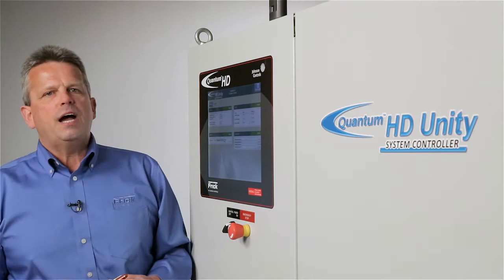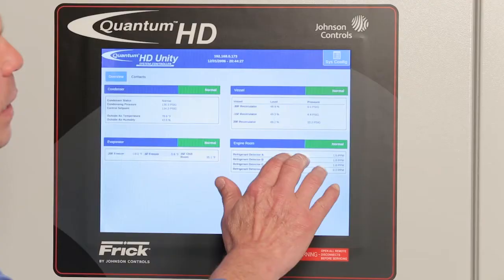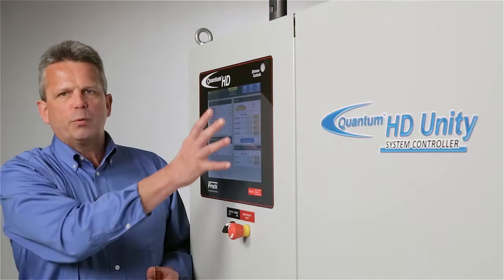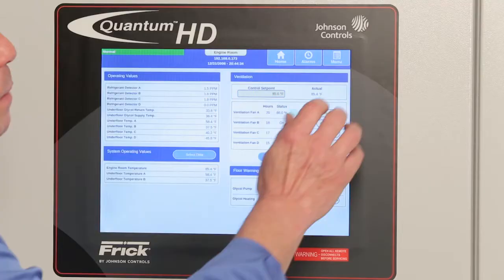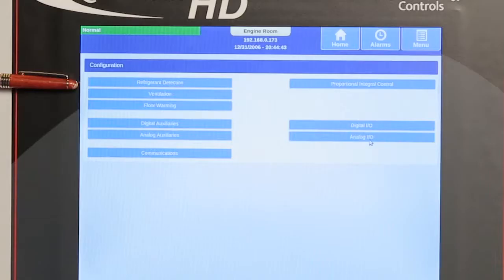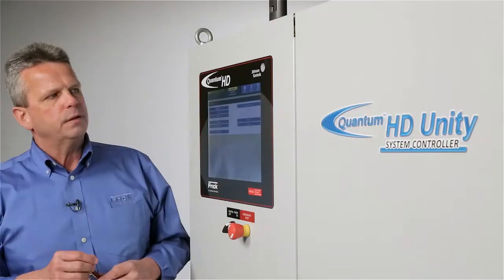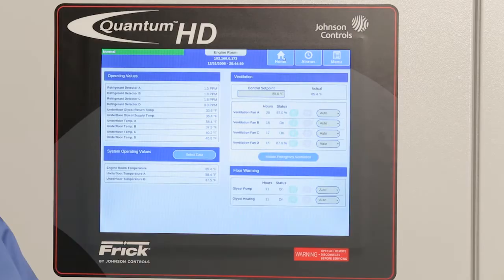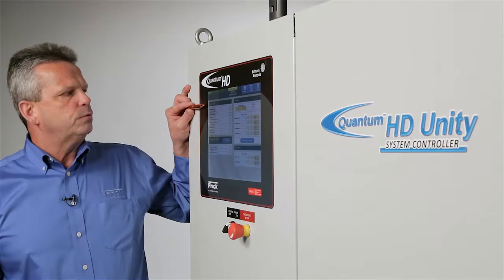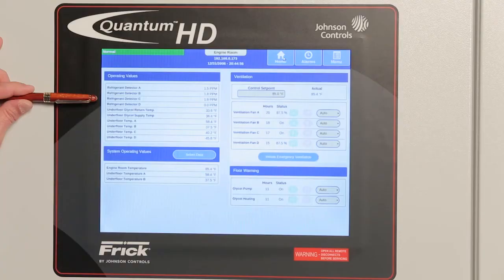At this time, we'd like to take a look at the engine room control. To get there, you touch anywhere in the engine room control section and you can see the home screen. But before we look at that, let's go back into menu and configuration. The three main parts of configuration for the engine room control are refrigerant detection, ventilation control, and floor warming. Going to the home screen, our operating values show the refrigerant detectors — we can do up to four of those — along with under-floor glycol return temp and supply temp, as well as under-floor temperature readings, up to four of those.